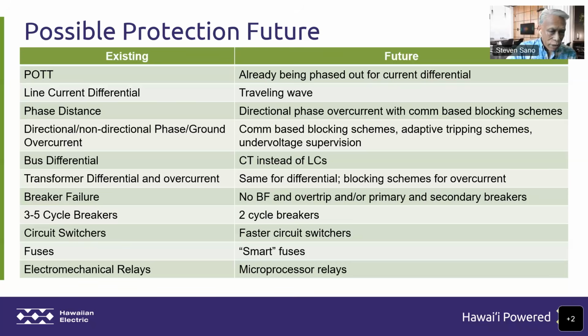Breaker failure. Again, I think I mentioned it adds additional time, which we may not have because critical clearing times are getting shorter. We may have to forego breaker failure or overtrip, have primary and secondary breakers, add a second breaker, make it redundant. 3 to 5 cycle breakers, again, if speed is going to be an issue, we'll have to go faster, convert to 2 cycle breakers. Circuit switchers, again, same issue there, speed of operation.